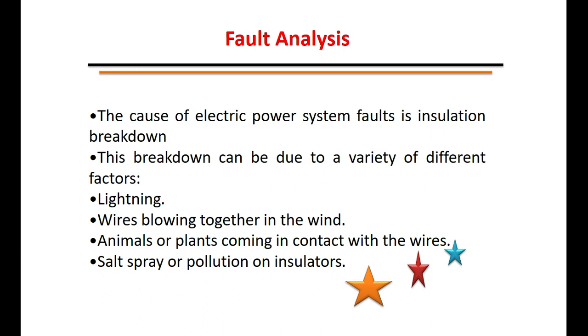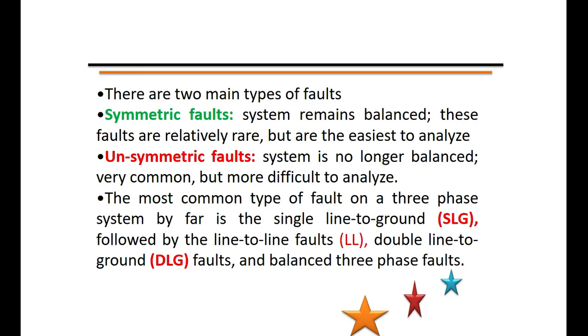Because of these faults, a heavy current will flow. If the fault is balanced in nature, then analysis is made on a per-phase basis. There are mainly two types of faults occurring in the system. One is the symmetrical fault, where the system remains balanced. These faults are relatively rare — only about 5% of faults are symmetrical in nature — but they are the easiest to analyze and can be solved on a per-phase basis.